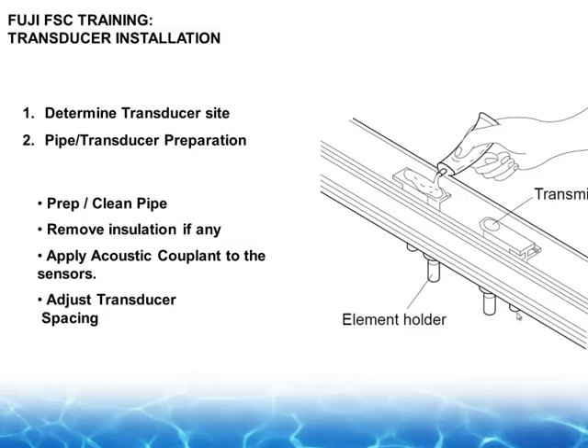The transducers do need an acoustic couplant. Before you put that on, you've got to wipe the surface clean. Don't bring your grinders anymore. It's old news. Just a rag and maybe a wire brush. Anything that's loose, knock it off the pipe. Don't worry about the paint. Put on an acoustic couplant. Why do we need an acoustic couplant? Well, let's see.